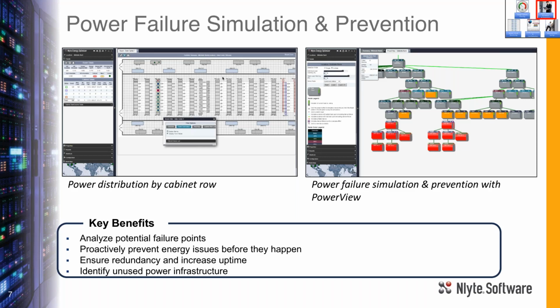Yeah, so just like every data center out there, they diversify power, and things are a little unique to everyone. For us at First American, we actually have four different power feeds coming in, and that creates a complicated situation where we have four generators, four UPSs, four switch gears. They're all dedicated, which is nice and creates a good sense of security, but at the same time, as you go upstream, it can create a problem when you diversify power, making sure each critical piece of equipment is on the right circuit, so that if something were to happen, we could still operate that server, that switch, that critical equipment.